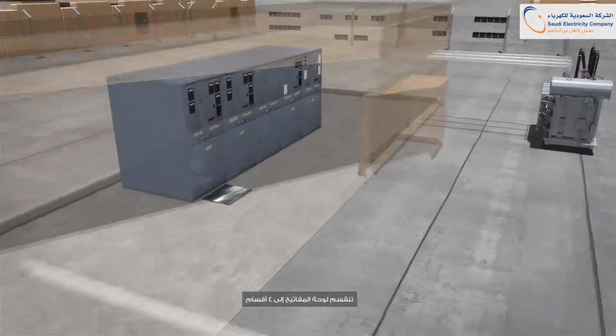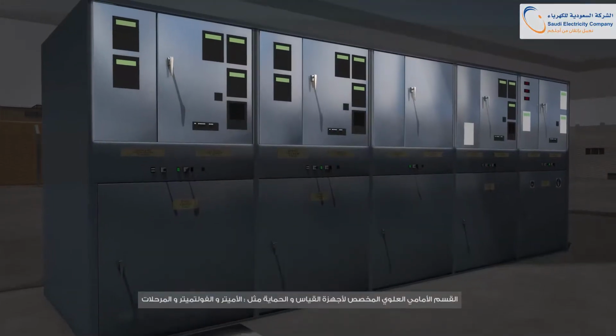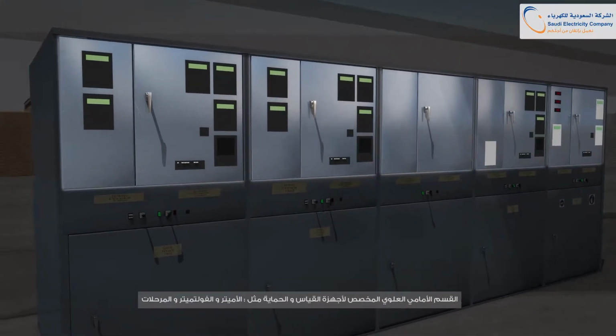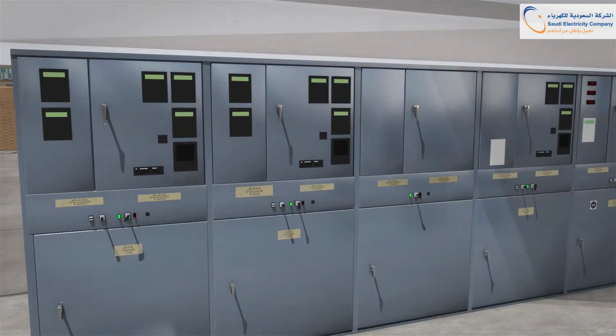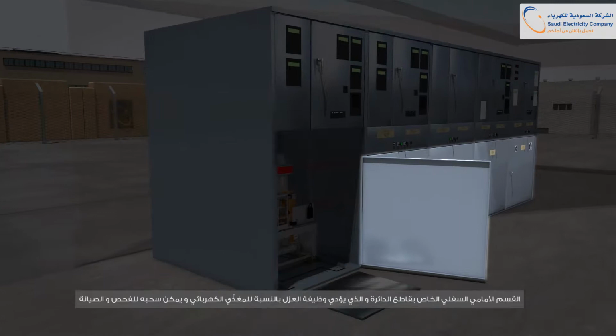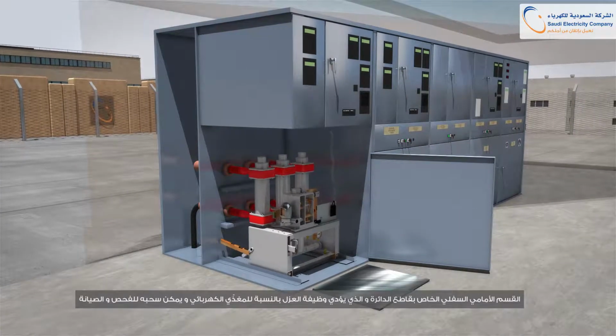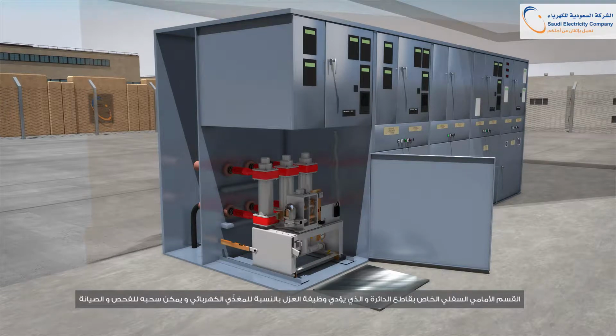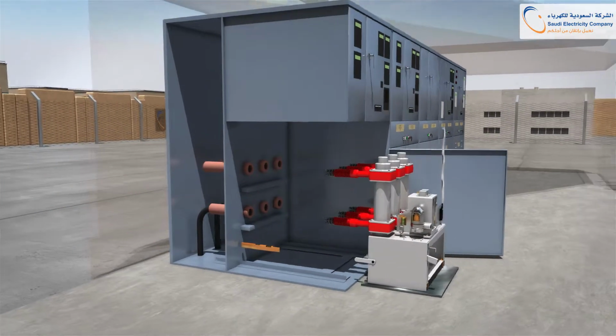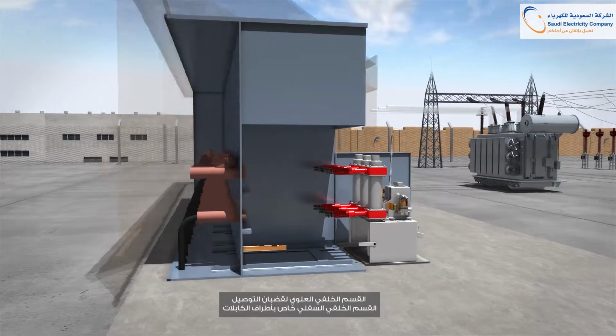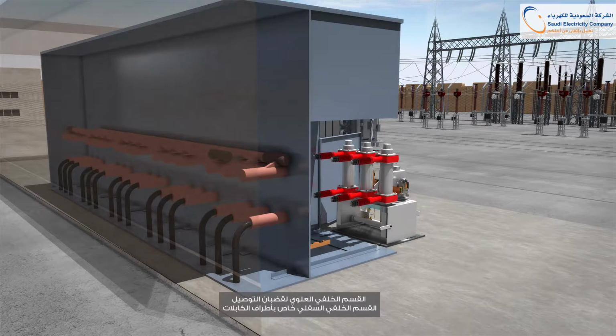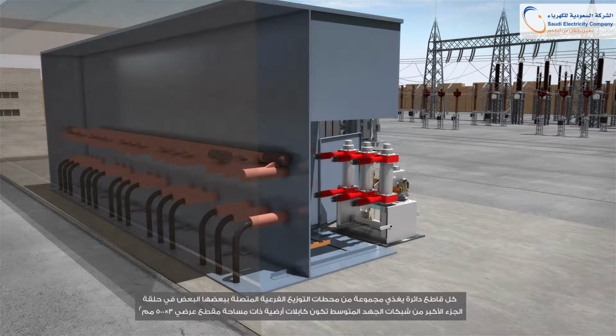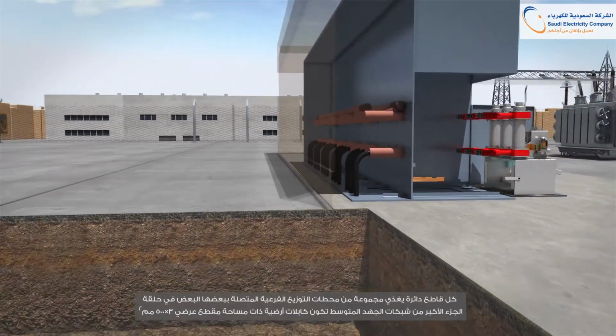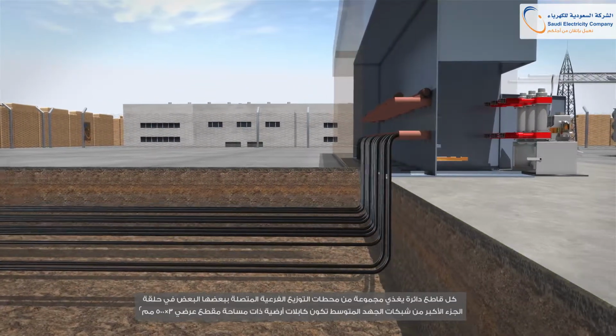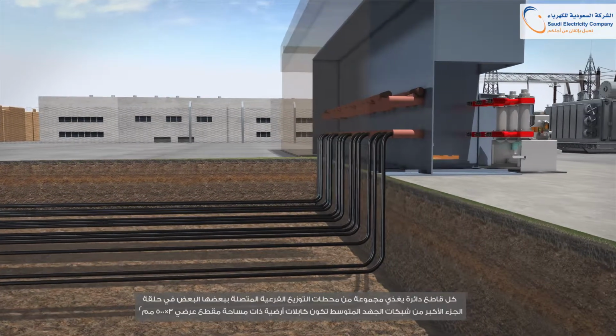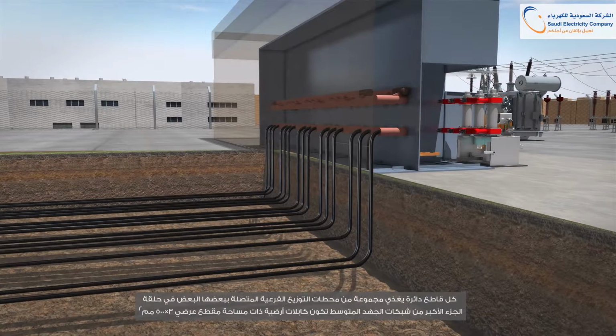The switchgear is divided into four compartments. The front upper compartment is for protective and measuring instruments, such as ammeter, voltmeter, and relays. The front lower compartment is for circuit breakers, which perform the isolator function of the feeders and can be withdrawn for inspection and maintenance. The rear upper compartment is for bus bars, and the rear lower compartment is for cable terminals. Each circuit breaker feeds a group of distribution substations, which are connected together as a ring. The majority of medium voltage networks are underground cables, which have a cross-section area of 3 by 500 square millimeters.